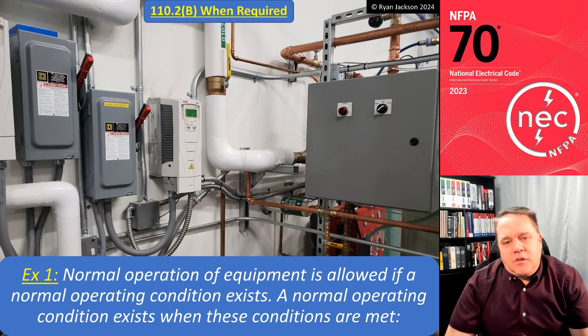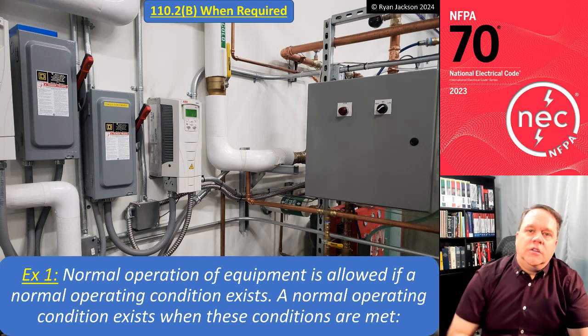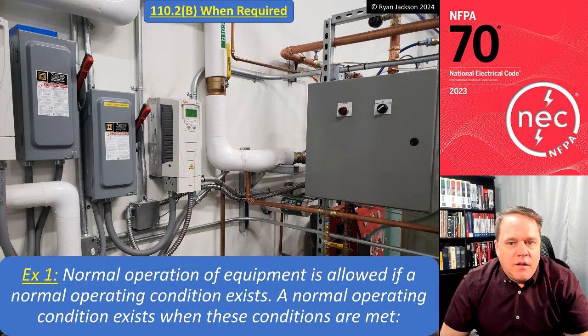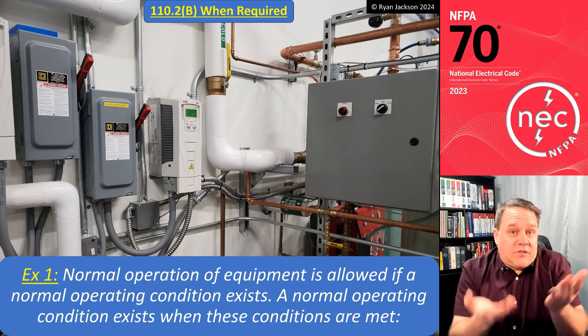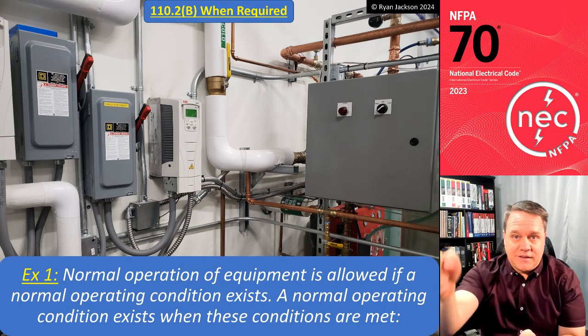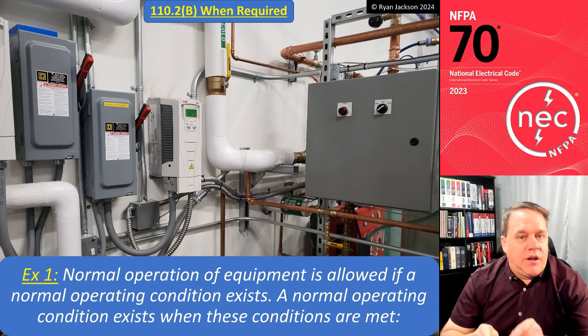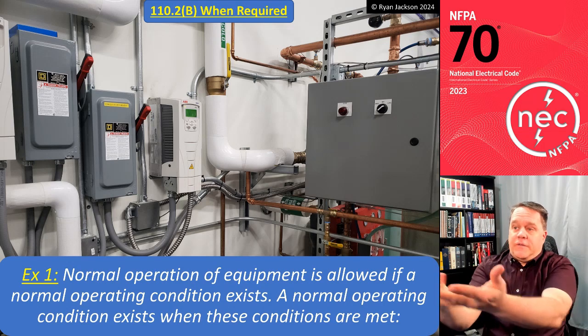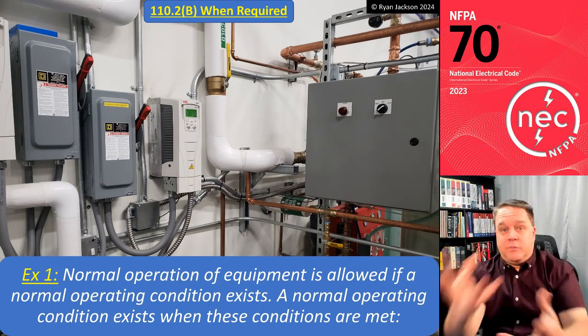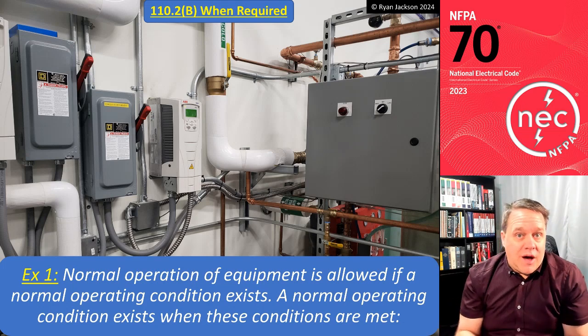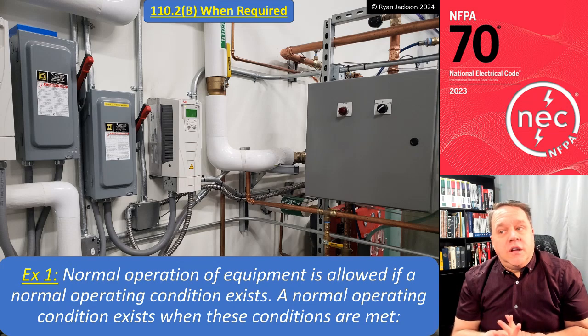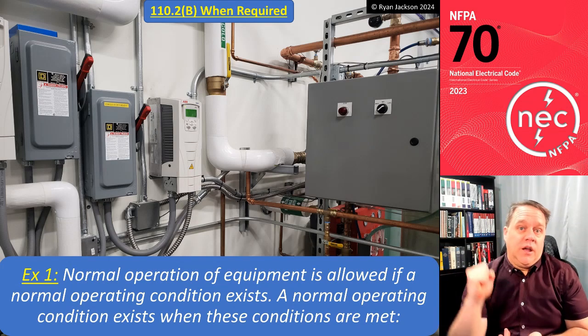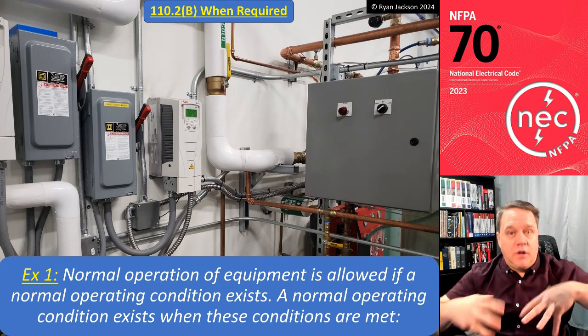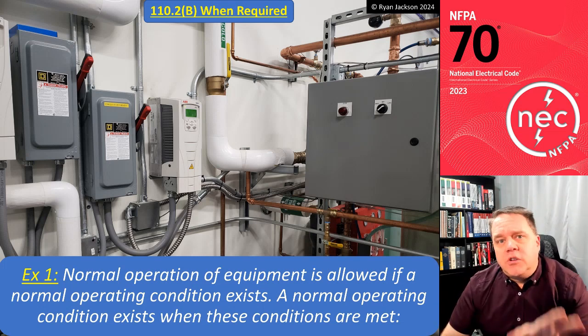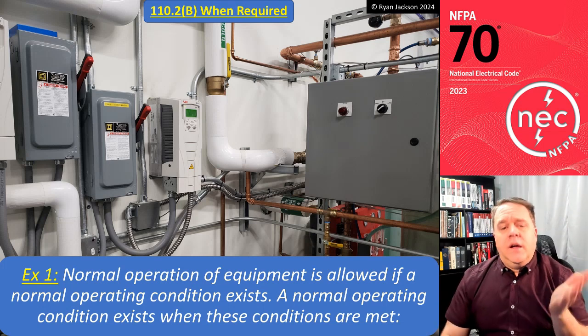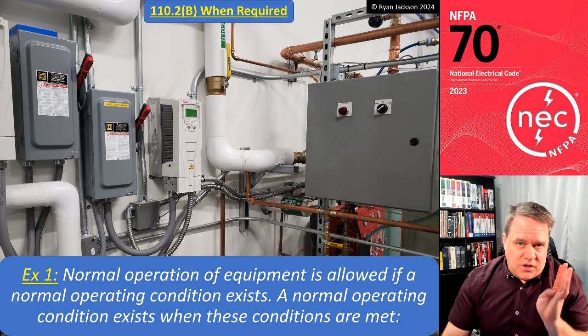Can I walk up to those disconnects here in the picture and use the disconnects? Yeah, that's normal operation of equipment, right? That's what it's for, is to disconnect it as long as a normal operating condition exists. Now look, if this thing is rusted out and there's exposed parts and it looks like it's ready to blow up, that's not a normal operating condition. So no, you couldn't just go up to it and work the handle. You'd have to shut it off and dress up, right? But normal operation of equipment is allowed if a normal operating condition exists.